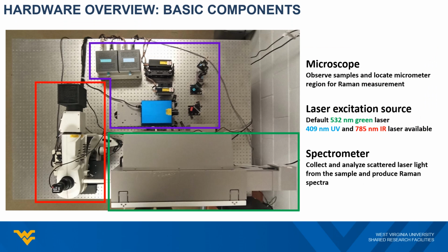Now let's take a look at the instrument on top of the optical table. Our Raman microscope consists of three basic components. The microscope, which will allow users to observe the sample and locate micrometer size region for Raman measurement. The laser excitation source used to generate Raman scattering from the sample. And the spectrometer that will collect and analyze the scattered Raman signal from the sample and produce the result spectra.